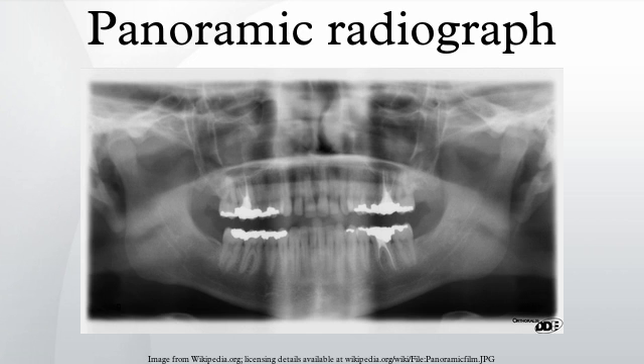Dental panoramic radiography equipment consists of a horizontal rotating arm which holds an X-ray source and a moving film mechanism arranged at opposed extremities. The patient's skull sits between the X-ray generator and the film. The X-ray source is collimated towards the film to give a beam shaped as a vertical blade having a width of 4–7 mm when arriving on the film after crossing the patient's skull. The height of that beam covers the mandibles and the maxilla regions.